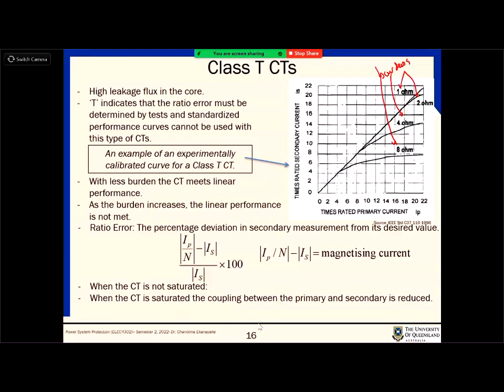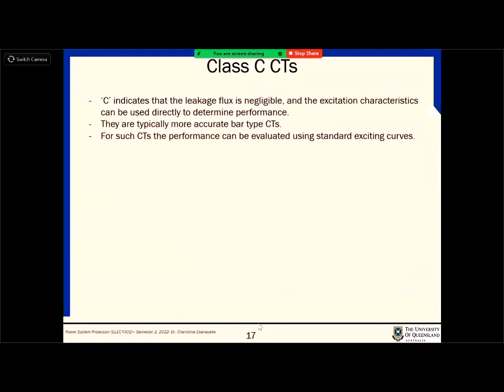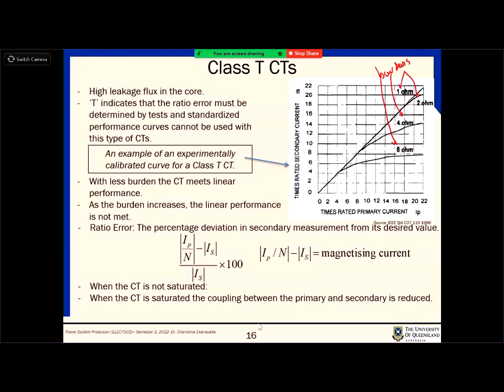And then, when the CT is saturated, the coupling between the primary and secondary is reduced. It's not 100% coupled. That's why you can see that when the current is a certain magnitude, the secondary is not going 100% as before, right? So the magnetic coupling is less.